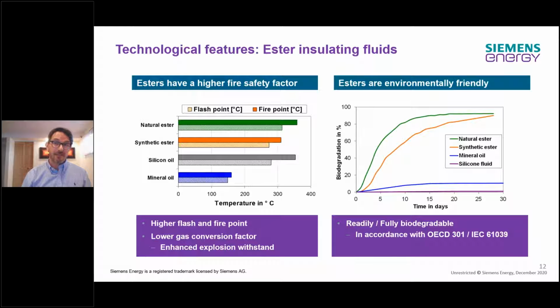Additionally, esters have a lower gas generation rate, which means that in case of an arc flash inside the transformer tank, they produce fewer gas bubbles than mineral oil, and so the explosion risk is also lower. And esters, as I mentioned, are environmentally friendly. And what does environmentally friendly mean?